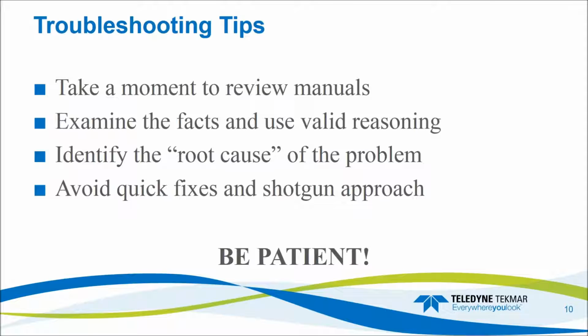Lastly, avoid quick fixes and don't take the shotgun approach. It's really important that we get to the core of the problem and really understand the root cause. Because if it turns out it's dirty glassware, which is caused by insufficient cleaning technique, that's something you can correct, and then you can move forward and not have that problem repeat. Or if it turns out that you have a bad batch of calibration standards, rather than continuing to use them and continuing to see issues, we can eliminate those standards, purchase new, and correct that issue.